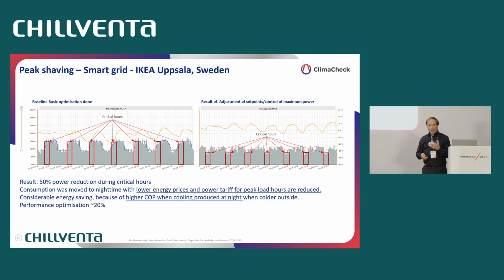This is another, where you apply performance analytics and strategies. Peak shaving. This is an IKEA store in Sweden. Looking at peak shaving, they could reduce the peak load between 8 and 11 in the morning by 50%. And they actually saved 20% of the energy because they were running more at night when it was colder outside. So it was extremely good proof that you need to look at your system. You need to be strategic in how you run them. It's not just allowing them to run.